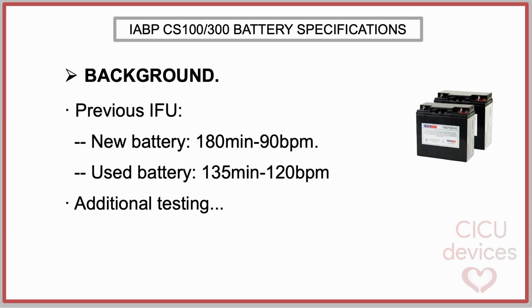Additional testing demonstrated that, throughout a 3-year service life, both new and previously used batteries consistently meet a minimum runtime of 135 minutes at 120 beats per minute, provided that scheduled preventive maintenance is performed. As a result, the distinction between new and used batteries was considered unnecessary and potentially confusing, prompting an update to the instructions for use specifications.